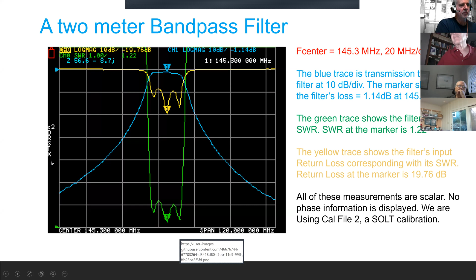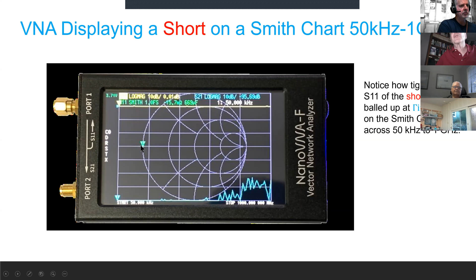Here is the VNA measuring a short circuit connected to port 1 on the Smith chart, and we're sweeping across the 50 kilohertz to 1 gigahertz frequency range. And you can see that it's all balled up right at 1 at 180 degrees, which is a short circuit on the Smith chart. That is really a decent measurement. You couldn't do that with the old 8410 system back in 1969.